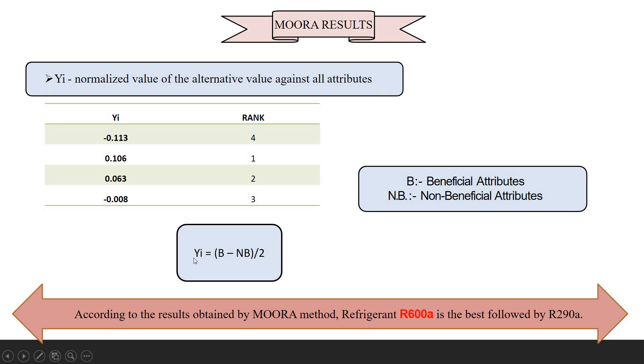According to the MOORA method, R600A is the best refrigerant, followed by R290, consistent with results from previous methods. These are the yi values and rankings for all refrigerants, with R600A achieving the first rank.